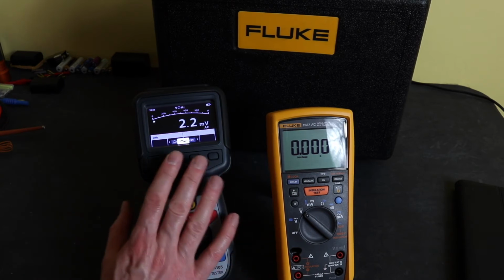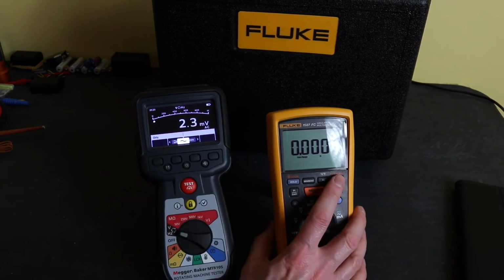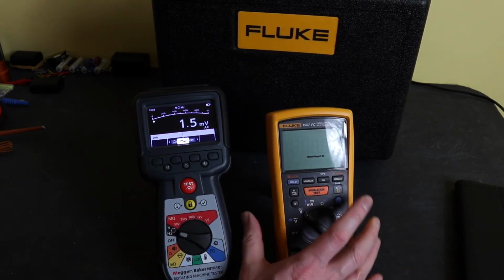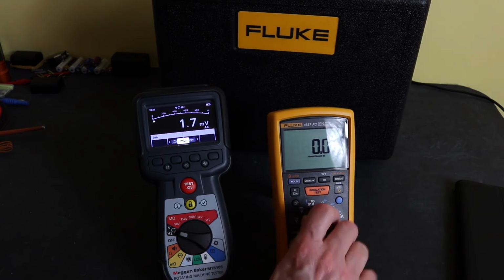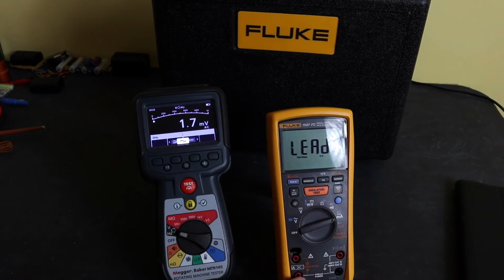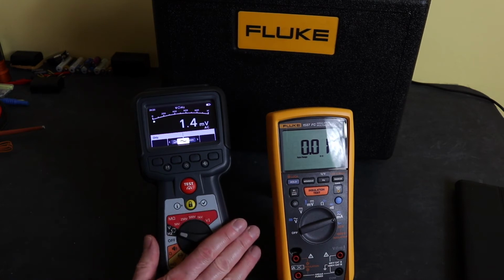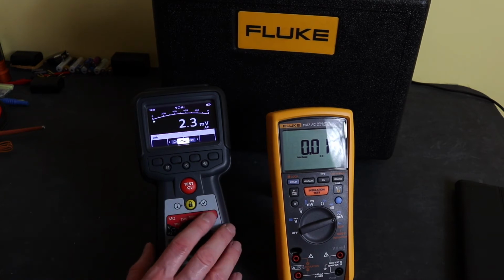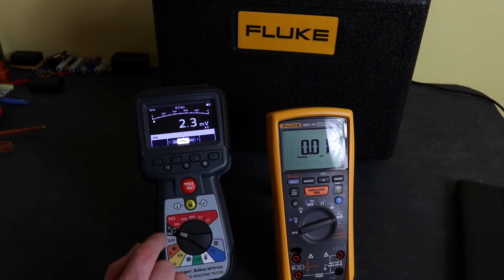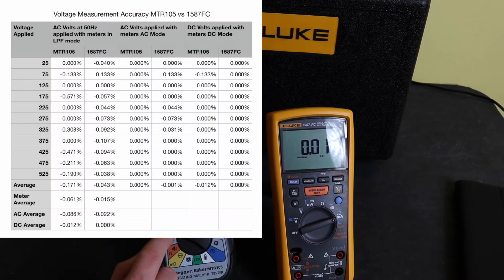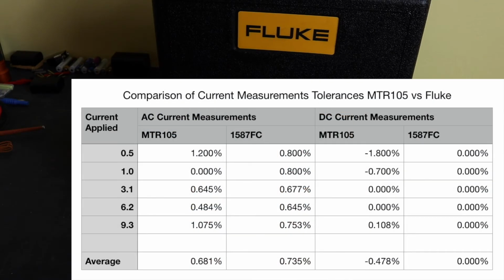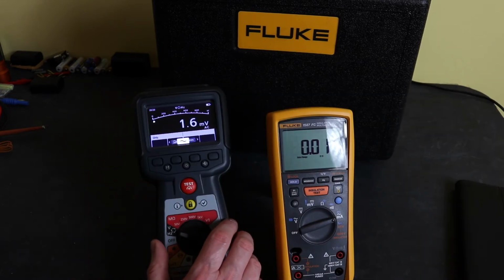Fully auto range, and you can't change range on this, whereas you can manually drive the range if you need to. This also has a current function, but only 400 milliamp current measurement. The Megger has no current capability whatsoever. In terms of accuracy for voltage and current, this Fluke is a little bit more accurate for both those functions than the Megger actually is.